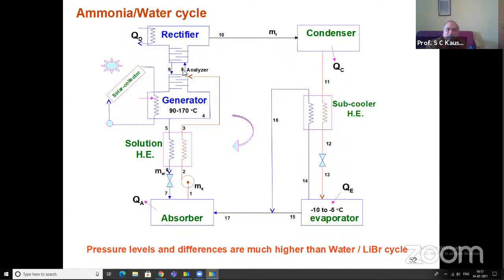Pressure levels are higher in the case of ammonia vapors, but the advantage is that we can operate the evaporator over a wide range of operating conditions, not only -5 to -10, we can go even to -22, say +20 degrees for the evaporator. It may not be a perfect rectification, but it is still working very well, even with 0.99 refrigerant concentration here. So the ammonia water cycle as well as the water lithium bromide cycle, these are the two options possible.